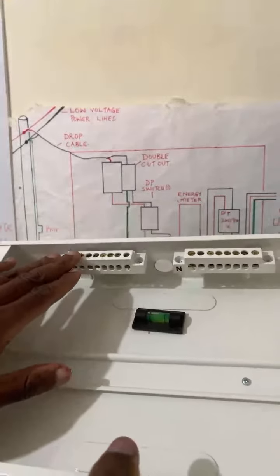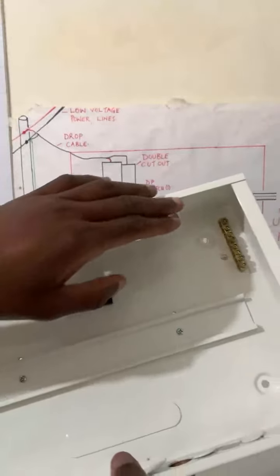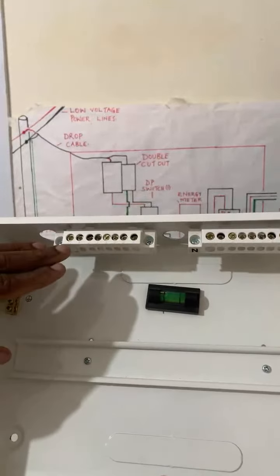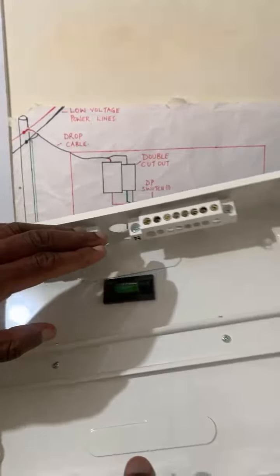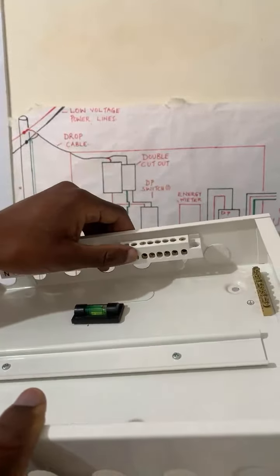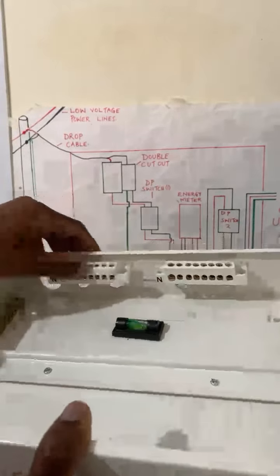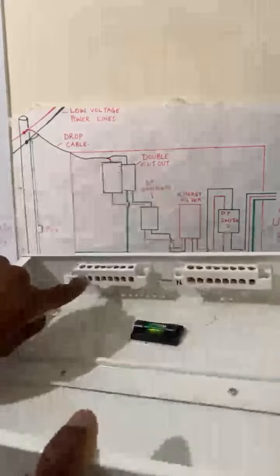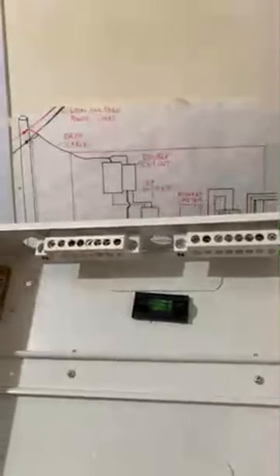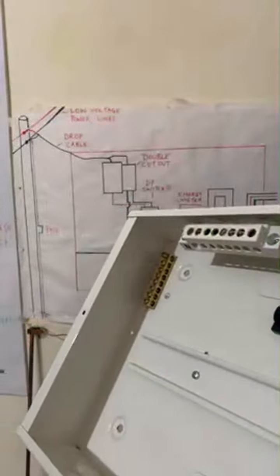You can see these are two neutral bars, so many connections. We did a lot of videos on the neutral. You can check them out on our channel, of course. So this neutral here can accommodate so many circuits returning to it, and the two neutral bars are bonded together so that when you feed the source, which is the neutral here, it is linked up to this neutral bar on this side, so that each and every circuit that is returning power is connected here, and that particular connection is perfect. Because today we are talking about earthing, look at that earth bar right there.